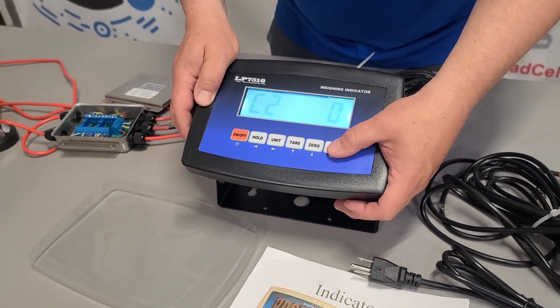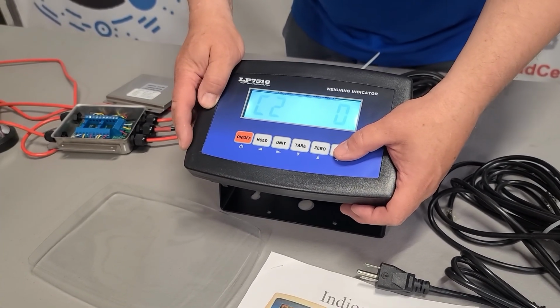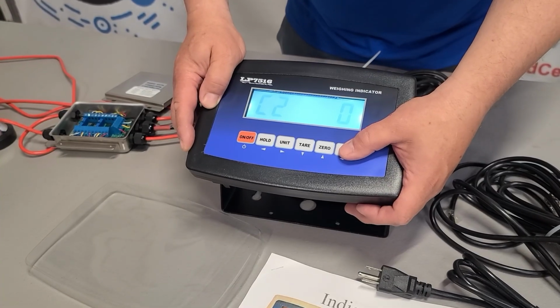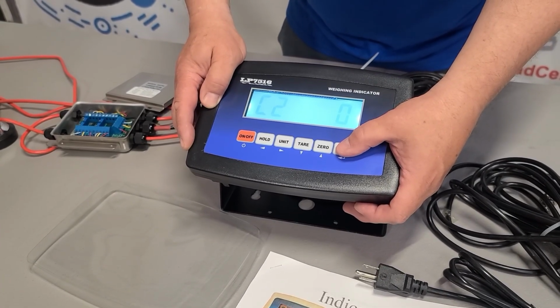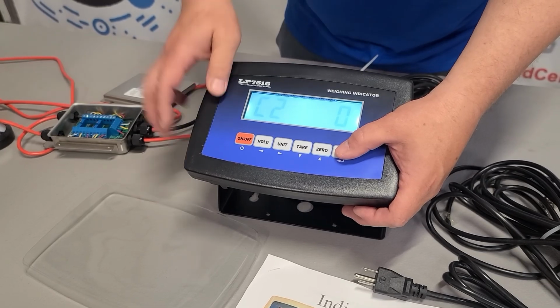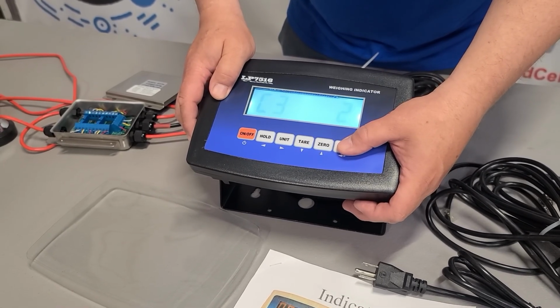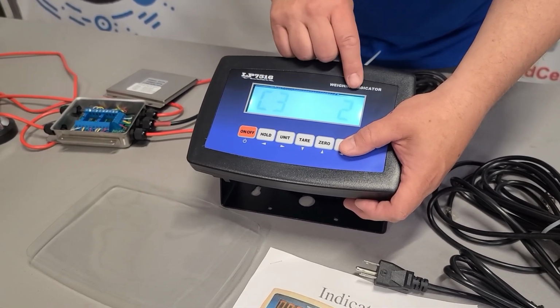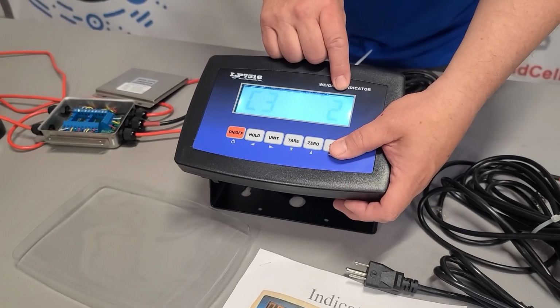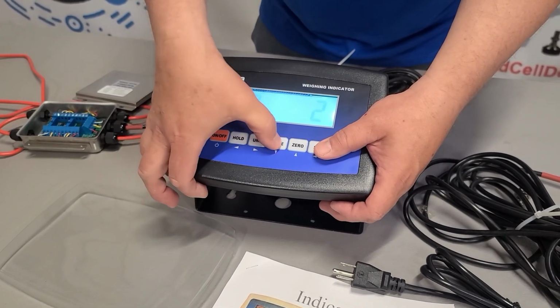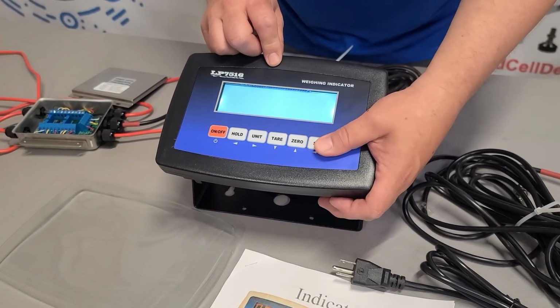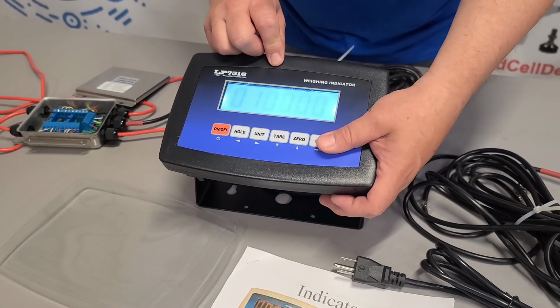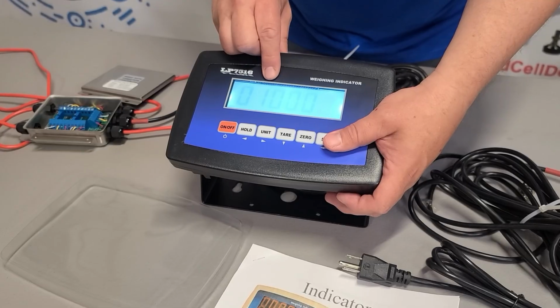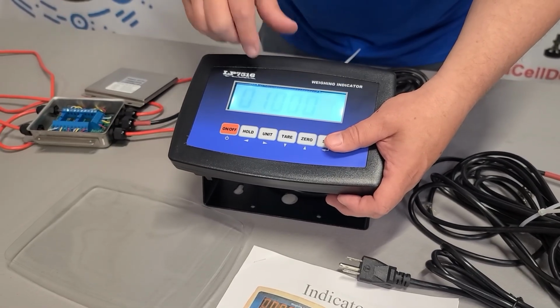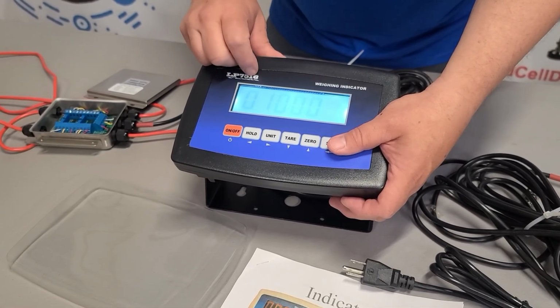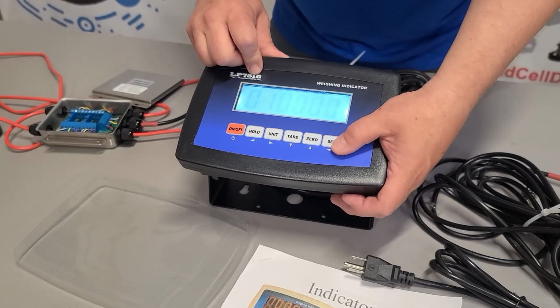C number 2 is going to give you how many decimal places we're going to have, the sensitivity of your scale. Well, we're going to weigh by 1 pound, so we're going to leave it at 0. Now, C3 tells you this one is actually set for 2 pound increment. So we're going to lower that to 1 pound. Number 4 is going to be your full scale capacity. We set this up to 10,000 pound. We have 5,000 pound load cells in there, so we could actually use 10,000 pound on this particular scale.